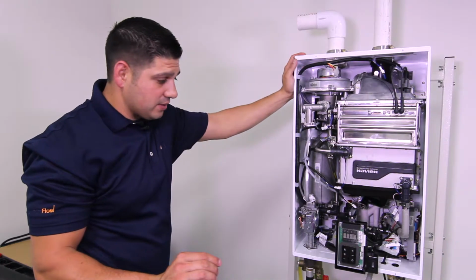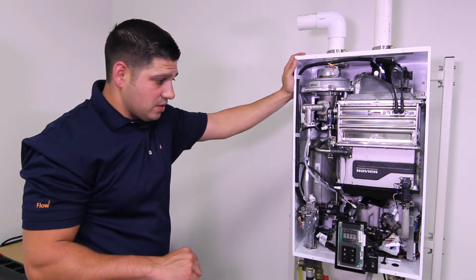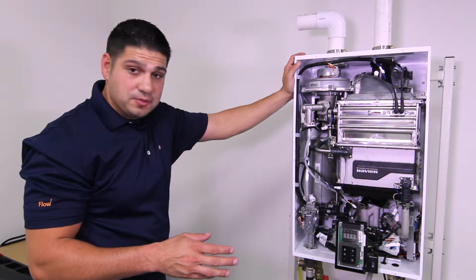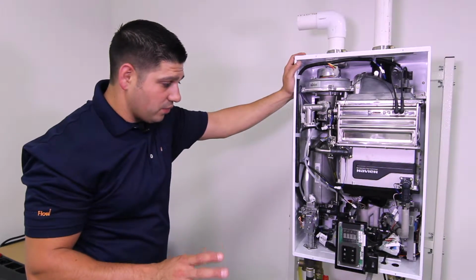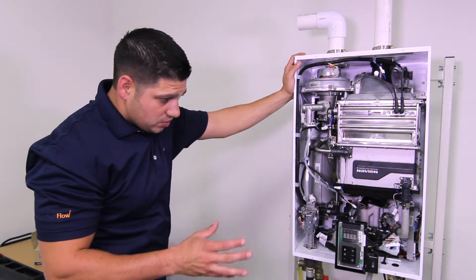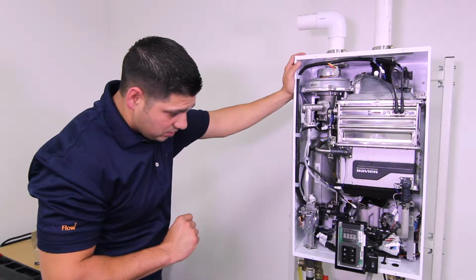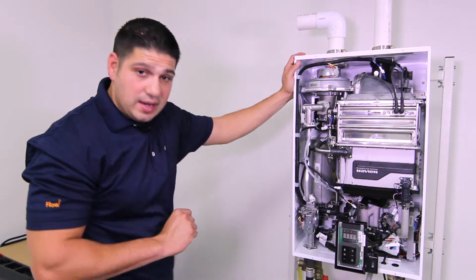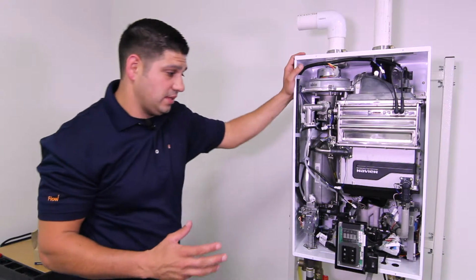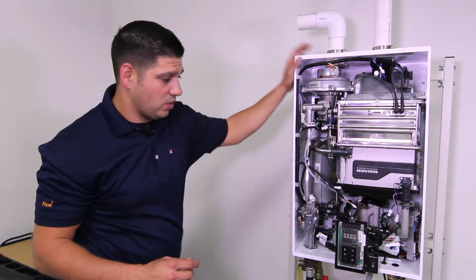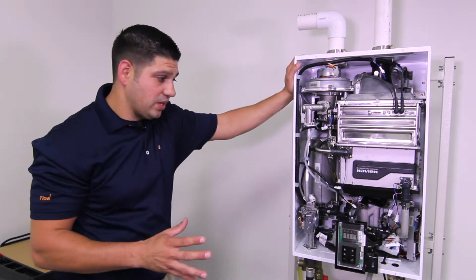So I barely cracked the inlet valve. The unit's slowly coming up to pressure, and all I'm waiting for is any drips or anything to show me that I didn't do a good job. So right now, I see no leaks. I see nothing that would tell me, I didn't want that to be pinched. I see nothing that would tell me that we have any kind of problems.